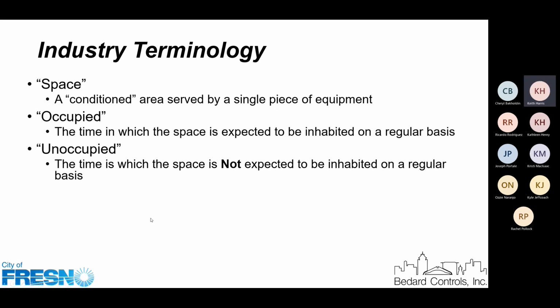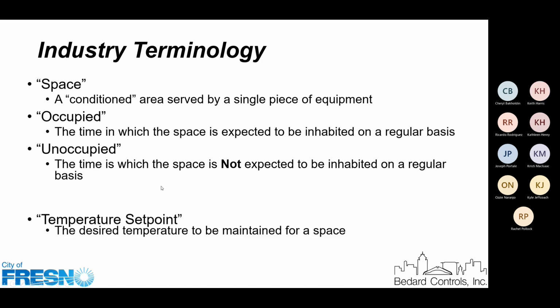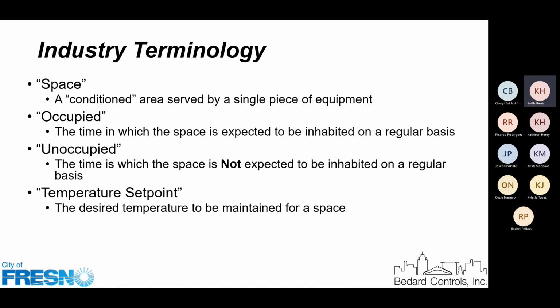So we'll use the term occupied and unoccupied. Typically in the parks world, I would think the occupied would be your normal business or open hours, and unoccupied would be after that. Now, typically, we don't turn off the equipment when unoccupied for a variety of reasons. We typically do what we call a setback, and a setback is a departure from the temperature set point that we want to maintain in the space when it's occupied.